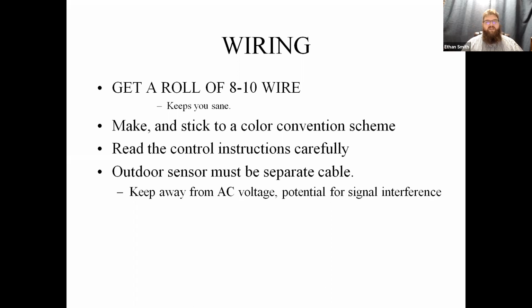If you are running an outdoor sensor, it must be run in a separate cable. If you run your outdoor sensor in the same cable as your control wires, the electromagnetic flux that you get off of those control wires will induce voltage into that sensor wire and cause your outdoor temperature sensor to read high or low, depending on whether you are energized or de-energized outside. I have run into a number of situations over the years where the outdoor temperature reads correctly as long as the heat pump isn't running. Once the heat pump starts up, outdoor temperature skyrockets or plummets, and it's all because we're running that sensor in the same cable. So make sure you're running a separate cable for outdoor temperature sensors.